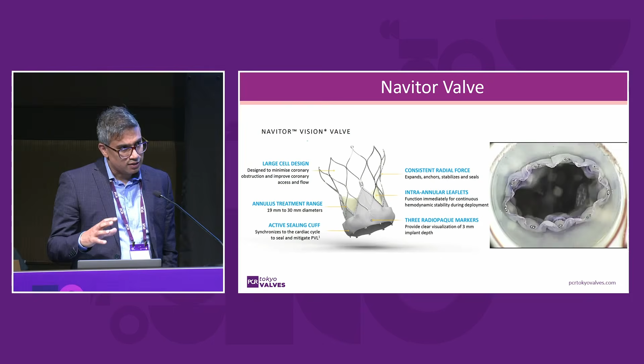It's got an active sealing cuff which expands during diastole, which really mitigates and seals off paravalvular leak, as well as in combination with the large cell design which can mould to calcium within the annulus complex. It's got a very good radial force, although the opening force may not be as high as other self-expanding platforms. It's got an excellent radial force that's nice and consistent and provides uniform expansion during deployment.